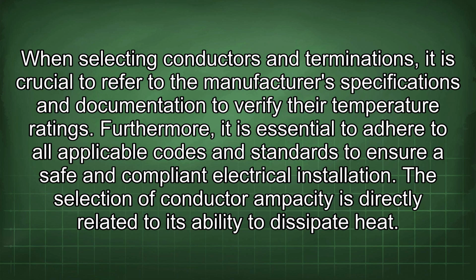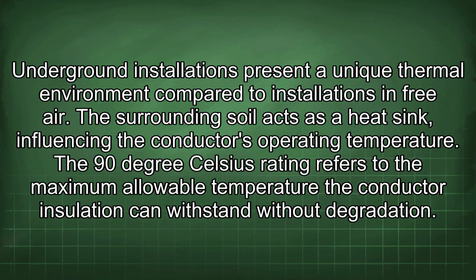When selecting conductors and terminations, it is crucial to refer to the manufacturer's specifications and documentation to verify the temperature ratings. Furthermore, it is essential to adhere to all applicable codes and standards to ensure a safe and compliant electrical installation. The selection of conductor ampacity is directly related to its ability to dissipate heat. Underground installations present a unique thermal environment compared to installations in free air. The surrounding soil acts as a heat sink, influencing the conductor's operating temperature.